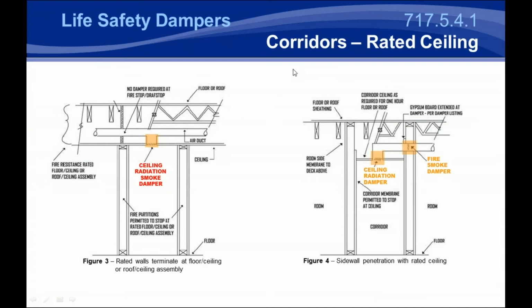Now, a little nuance to corridors is when they have a rated ceiling and a penetration in that rated ceiling. So if you've got a rated ceiling, and you're using the duct above to penetrate the ceiling membrane, you need a ceiling radiation damper. As you can see, there are two types. It's either when you penetrate the ceiling only, or when you penetrate the sidewall and the rated ceiling. Now, figure 4 is going to be the most common.